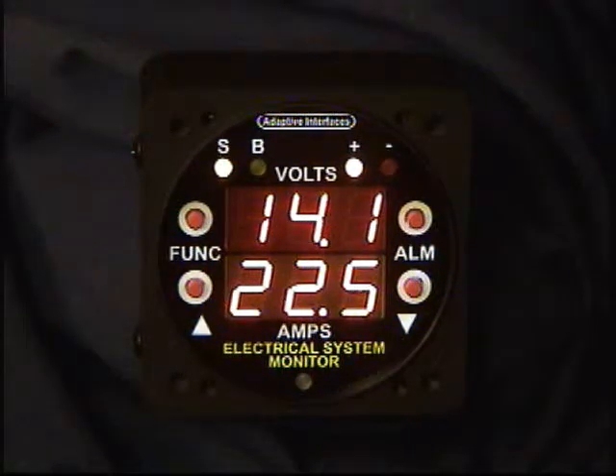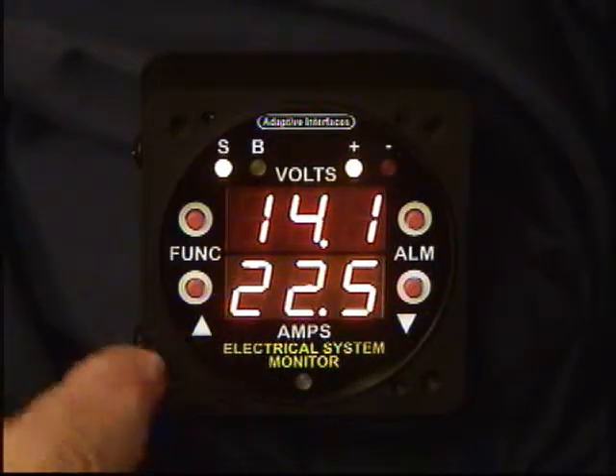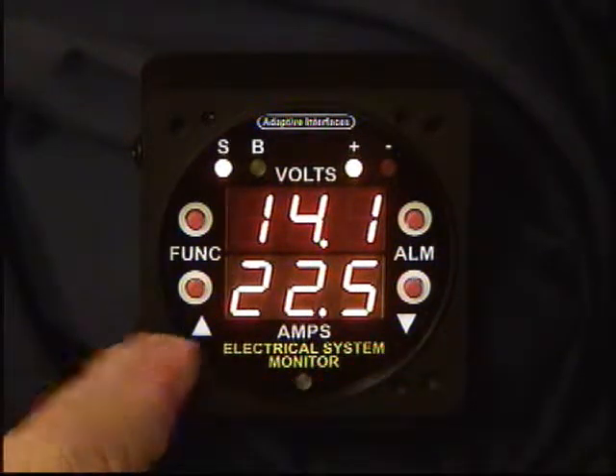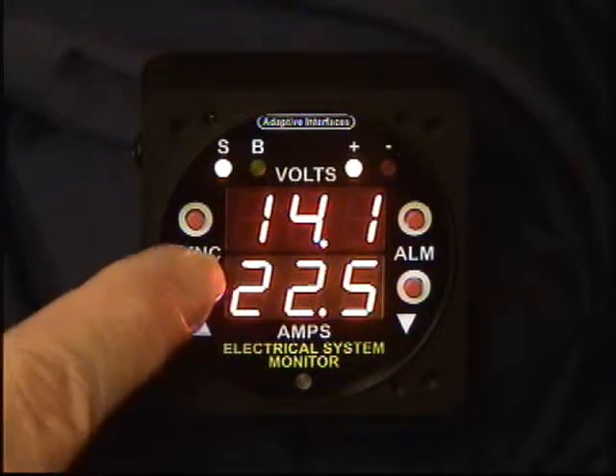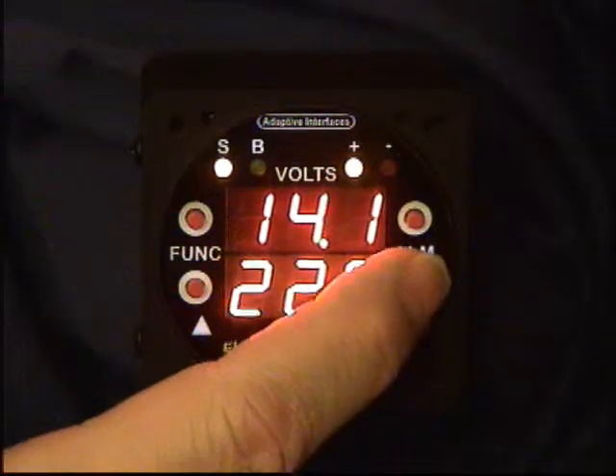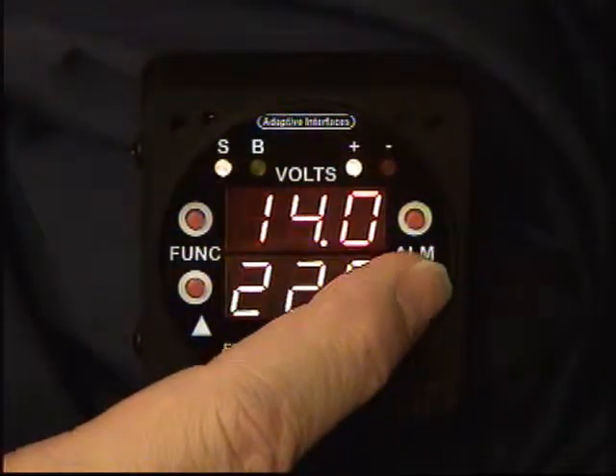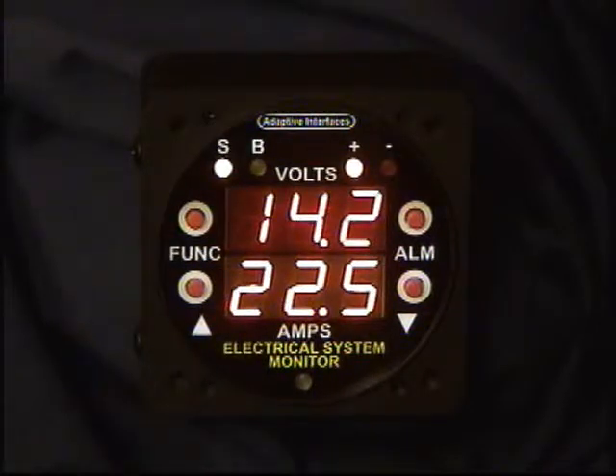Also, a separate control can be used to adjust the brightness of the display. Right now it's set for a front panel adjustment. Using the up and down arrows when it's in this normal operating mode will increase or decrease the brightness. There's also other ways of controlling the brightness, and we'll get into that next.